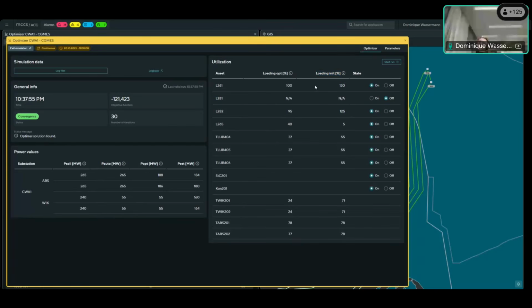But our optimization solution actually takes this into consideration. It is aware that line 281 is out of service and will artificially decrease the infeed of our wind parks so we can reach 100% line loading on line 261. The result is that we cannot fully infeed all of the power we could for Wikinger, but what we have achieved is operational security, and also the possibility for operators to avoid opening a manual tool to calculate set points and then type them into the SCADA system.